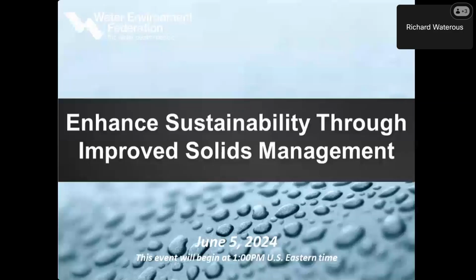Can you add the ferrous to the common DWC centrate piping for Struvite control and removal? Mark, it's a good question. First of all, it would be ferric chloride or ferric sulfate and not ferrous. It'd be Fe+3 for this application.